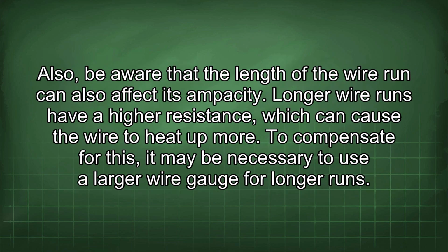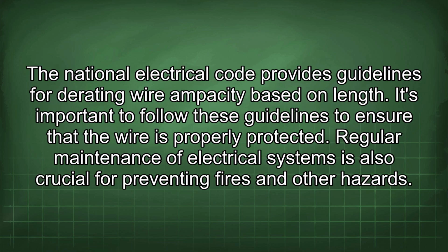Also, be aware that the length of the wire run can also affect its ampacity. Longer wire runs have a higher resistance, which can cause the wire to heat up more. To compensate for this, it may be necessary to use a larger wire gauge for longer runs. The National Electrical Code provides guidelines for derating wire ampacity based on length. It's important to follow these guidelines to ensure that the wire is properly protected.